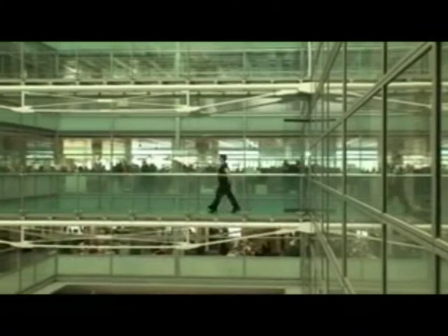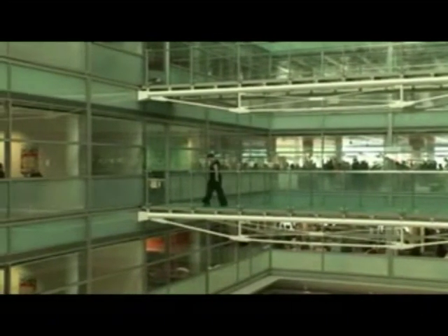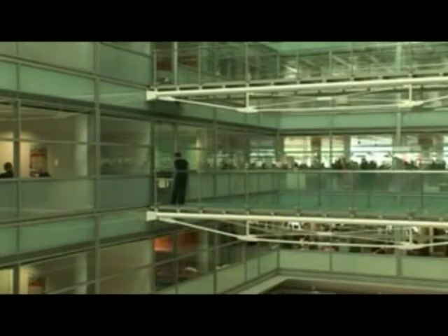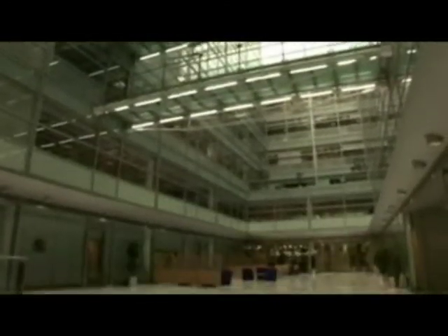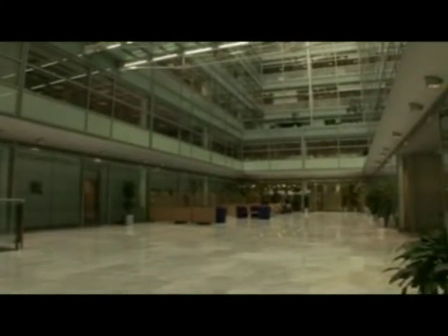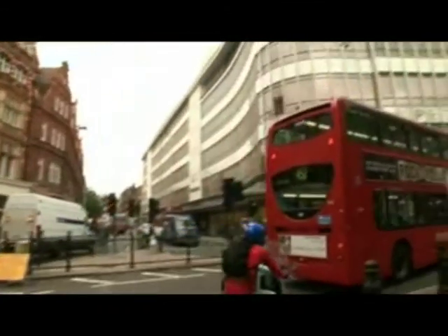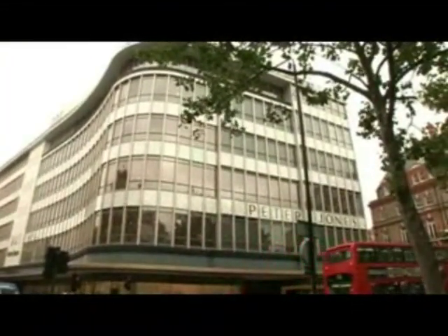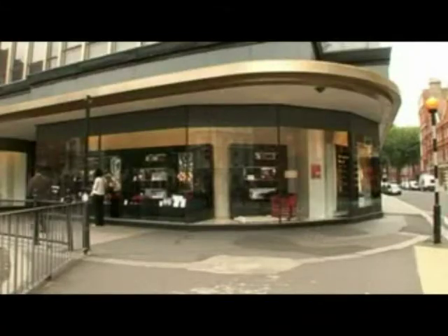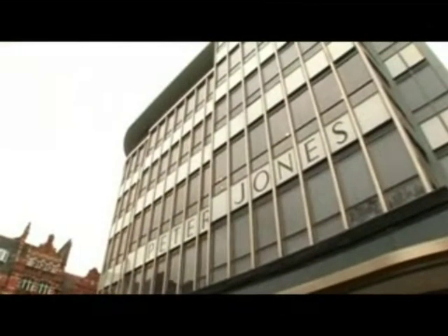As a guide, an air-conditioned general office area of 2,000 square metres or more is likely to require 250 kilowatts of capacity. A general office area of 200 square metres or more is likely to require 12 kilowatts of capacity. Buildings with high levels of IT or electrical equipment may exceed these capacities at lower floor areas. If you're not sure whether your air conditioning systems reach the threshold, you must determine the installed capacity of your system by appropriate inspection, calculation and inquiries.